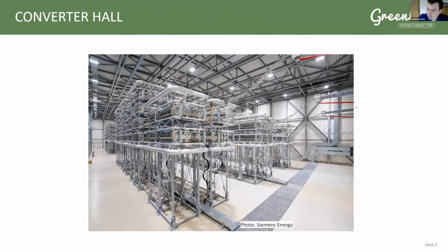This is an image from Siemens of what the inside of the DC hall will look like. And I know from visiting EWIC and other converter stations that this is quite an impressive sight when you see all of this power electronics hanging from the ceiling or attached to the floor in a huge valve hall like this. Here you can see the DC cable will come in at the back of this room, and you've got the three phases of the AC coming out here. You can just see on the top the red connections heading towards the three transformers for the three phases.